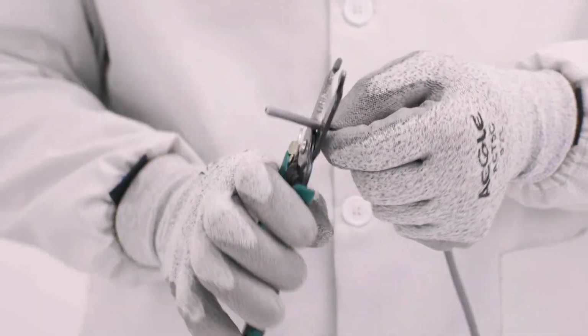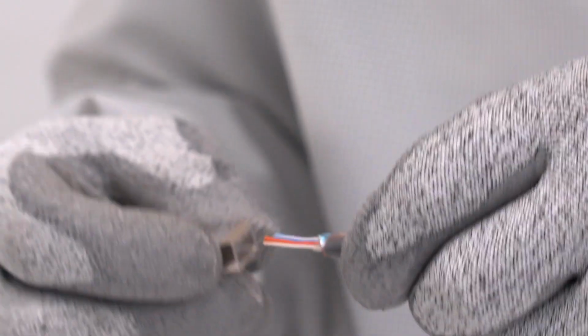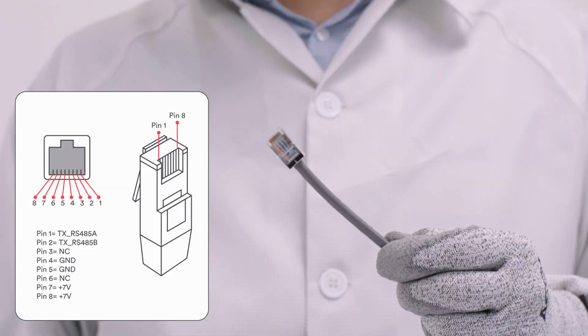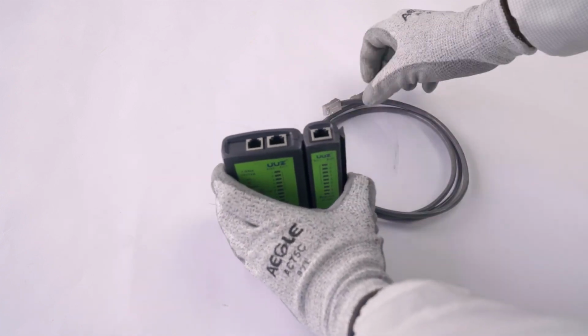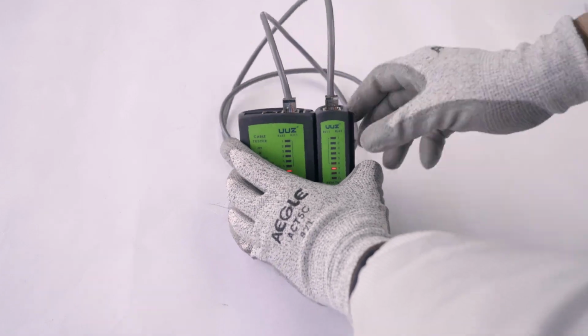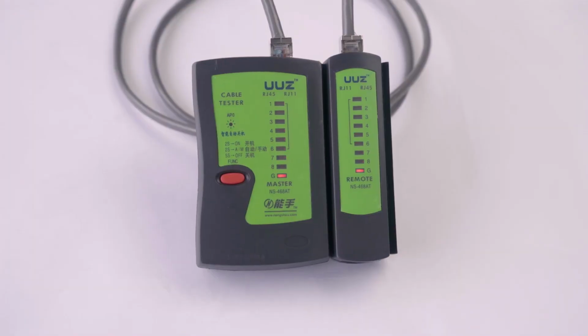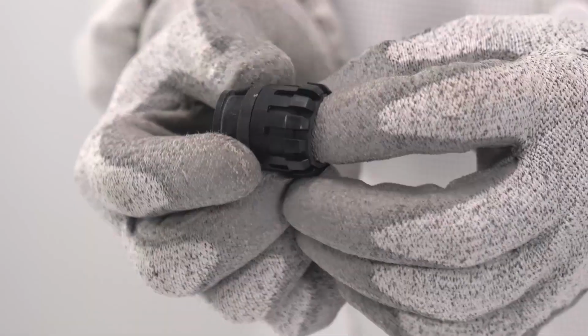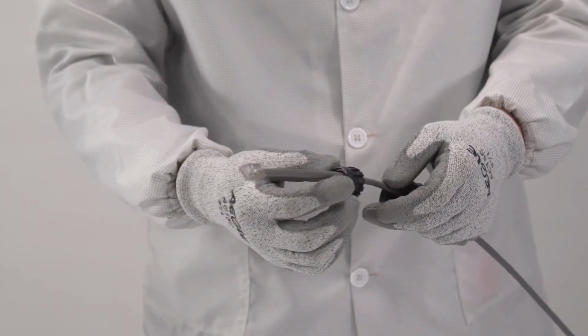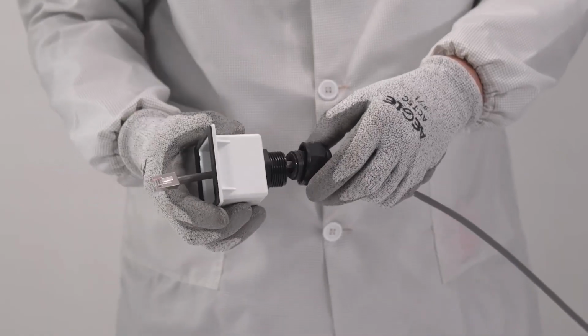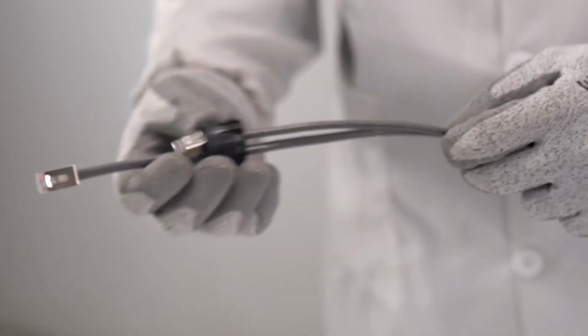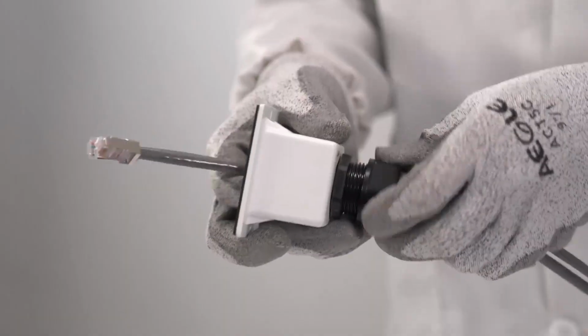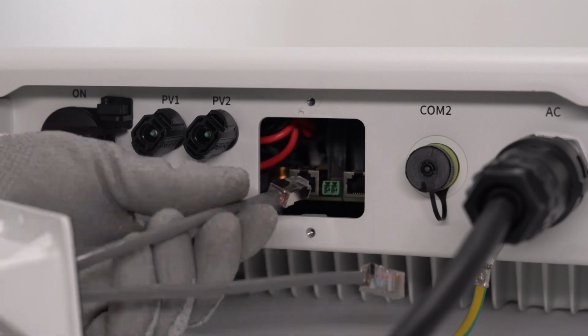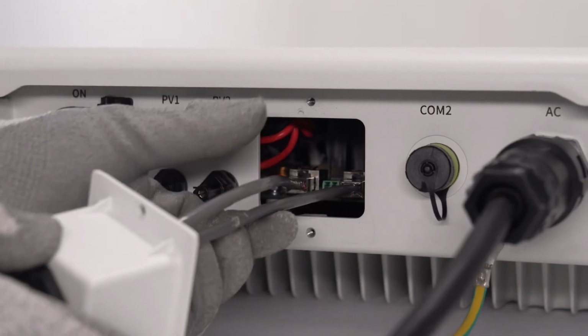RS485 cable pin assignment as below. Check the cable with the cable tester. Make sure the cable is connected. Loosen the swivel nut of the cable gland on the communication cover. Remove sealing plugs and lead the cable through the swivel nut, sealing ring, communication cover, and magnetic ring. Insert the cable into the socket. Attach the communication cover to the inverter with M4 screws and tighten the swivel nut.